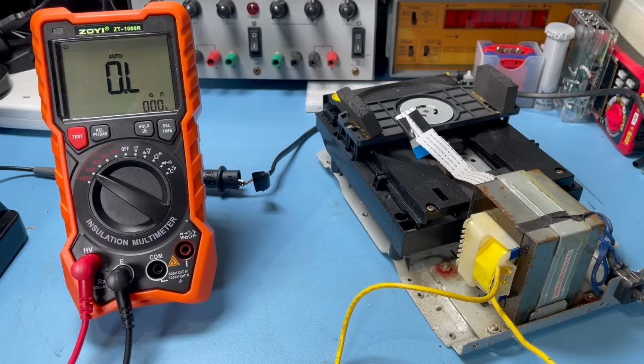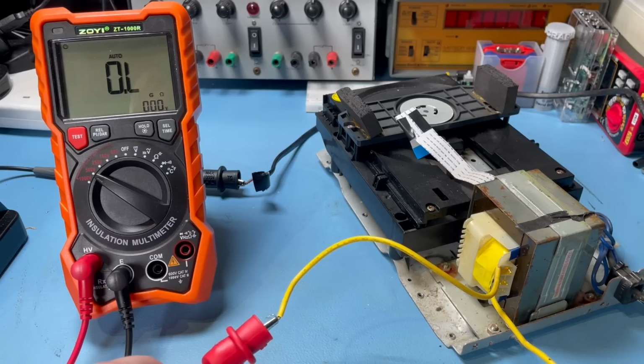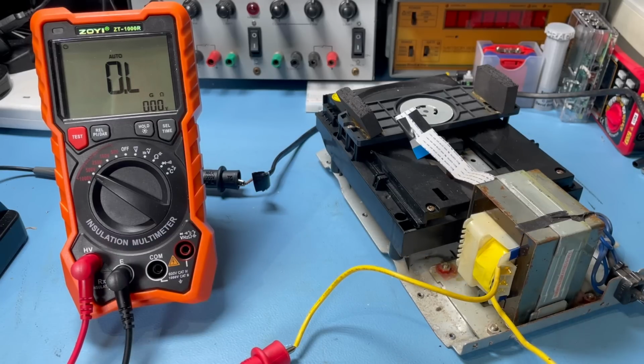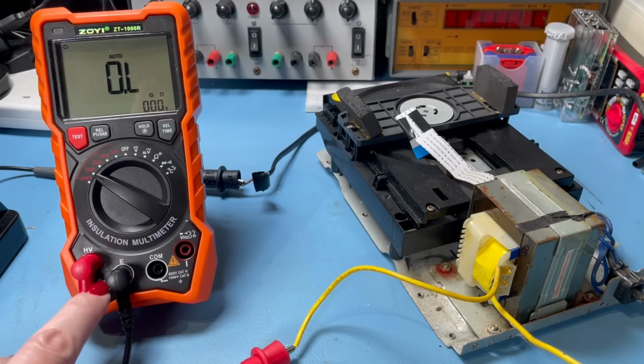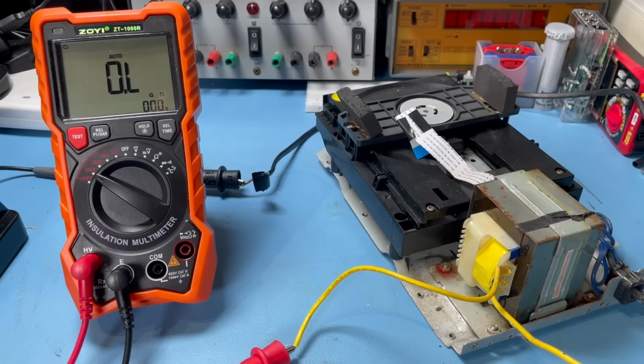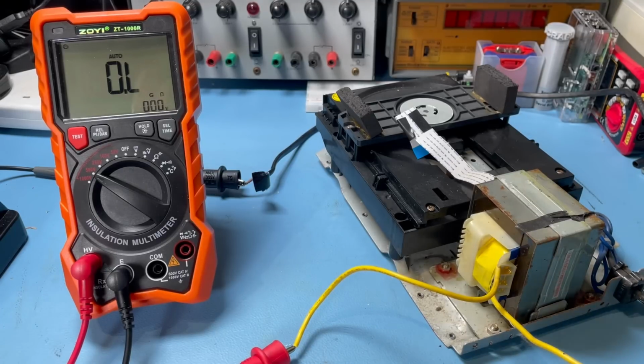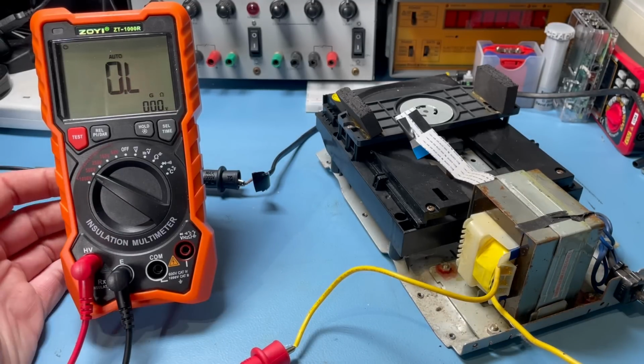Now, one thing to bear in mind is we're putting quite a lot of voltage into these cables. So you want to make sure that the other end is either taped up or safe somewhere, so someone's not going to grab hold of it, because that would be bad. And also, when you're testing, you'll get this red triangle on down here, which warns that it's putting out a high voltage. So when that is the case, don't touch any of the connections or the device under test, or you may get a nasty shock. And no one wants that.